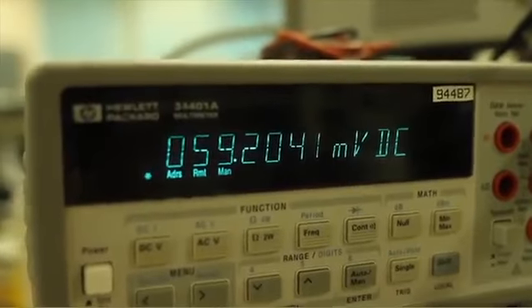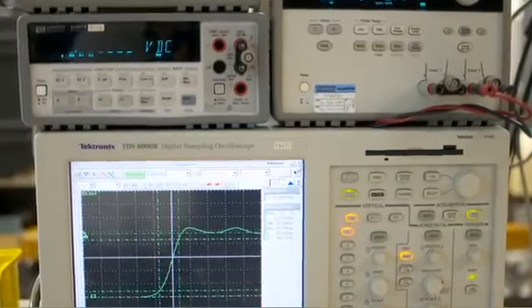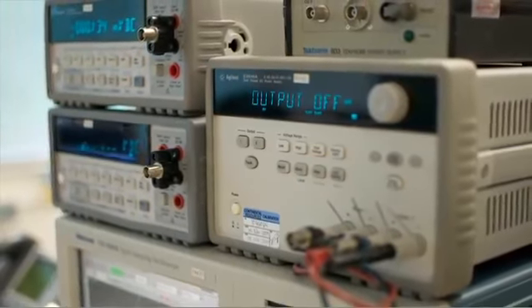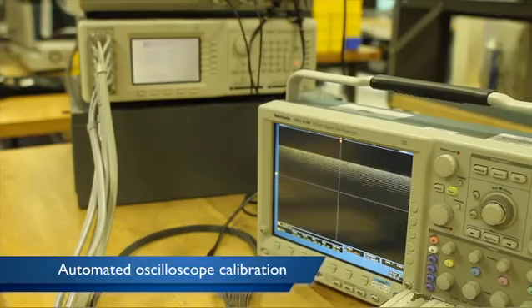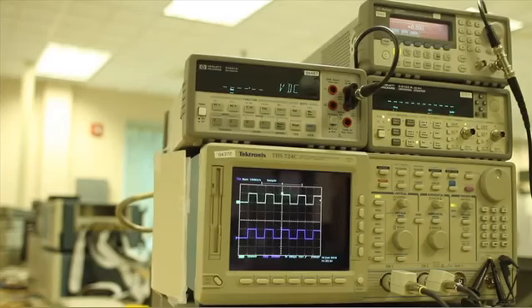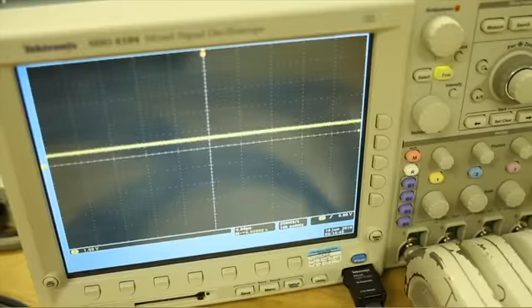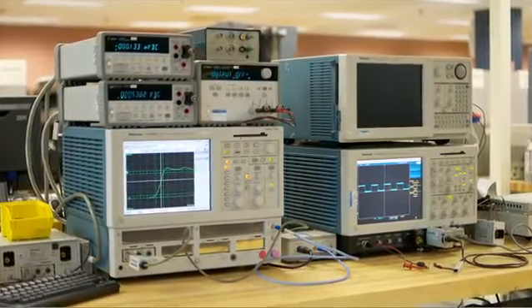We have an oscilloscope automated cal station that is able to calibrate a scope which would normally take 6 to 8 hours to do manually, which used to be the old way and is not practical any longer. We can do that now with the automated system in anywhere from an hour to an hour and a half, and that is with full test data. We send out a lot of scopes, and it's very important to have more than just one scope cal system.